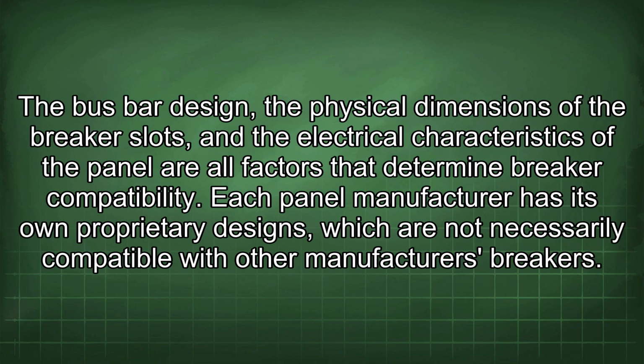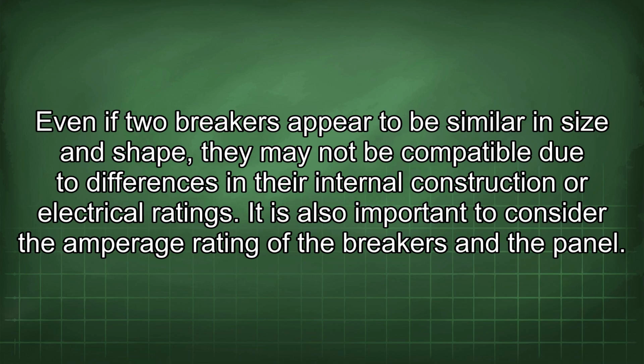The bus bar design, the physical dimensions of the breaker slots, and the electrical characteristics of the panel are all factors that determine breaker compatibility. Each panel manufacturer has its own proprietary designs, which are not necessarily compatible with other manufacturers' breakers. Even if two breakers appear to be similar in size and shape, they may not be compatible due to differences in their internal construction or electrical ratings.